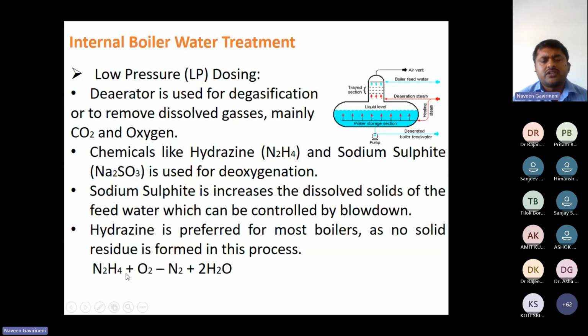N2H4 reacts directly with oxygen and is converted into N2 and 2H2O. The nitrogen gas goes out through the air vent, and the rest is converted into water. The deaerator is a part which is most important in the boiler power sector. Not only the power sector, the process sector also. Why?